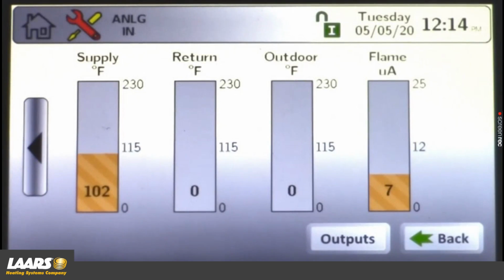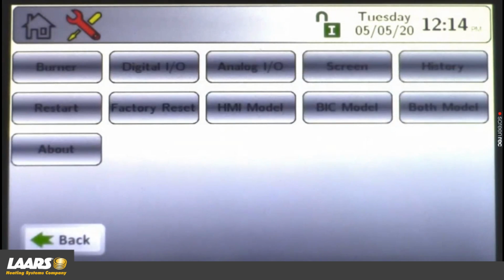And now you'll see that I gave it a call for heat. We went through the sequence of operation, and now we're actually getting a flame signal. I'm going to go back to the service menu. Okay, analog I/O, all of that information is right on your home screen as well. So we talked about inlet temperatures, outlet temperatures, flame signals. All of that is right on the home screen. However, we do have that also under service, so you can view that there.